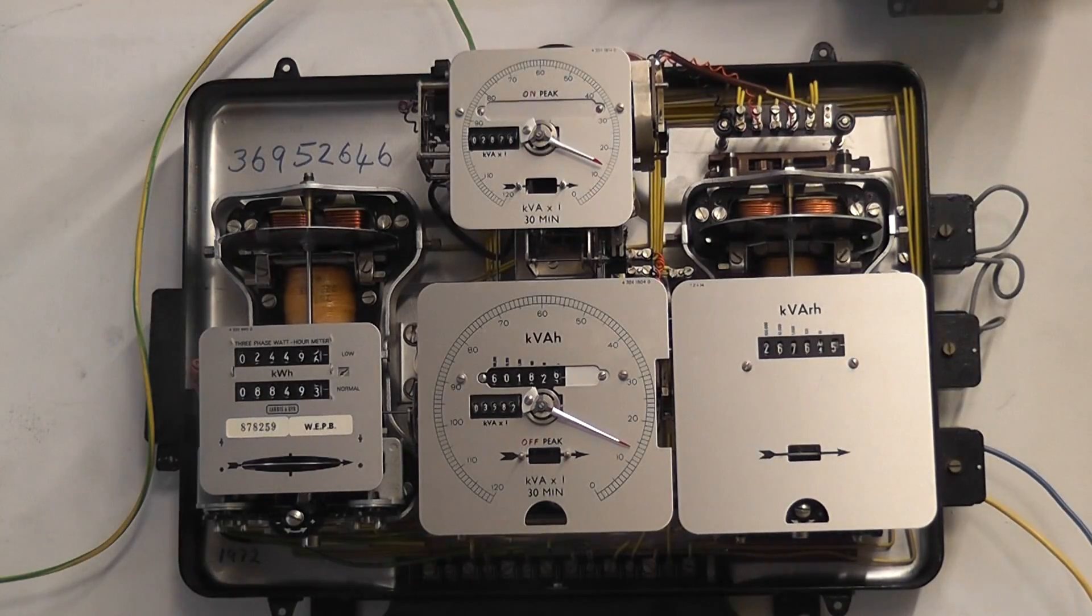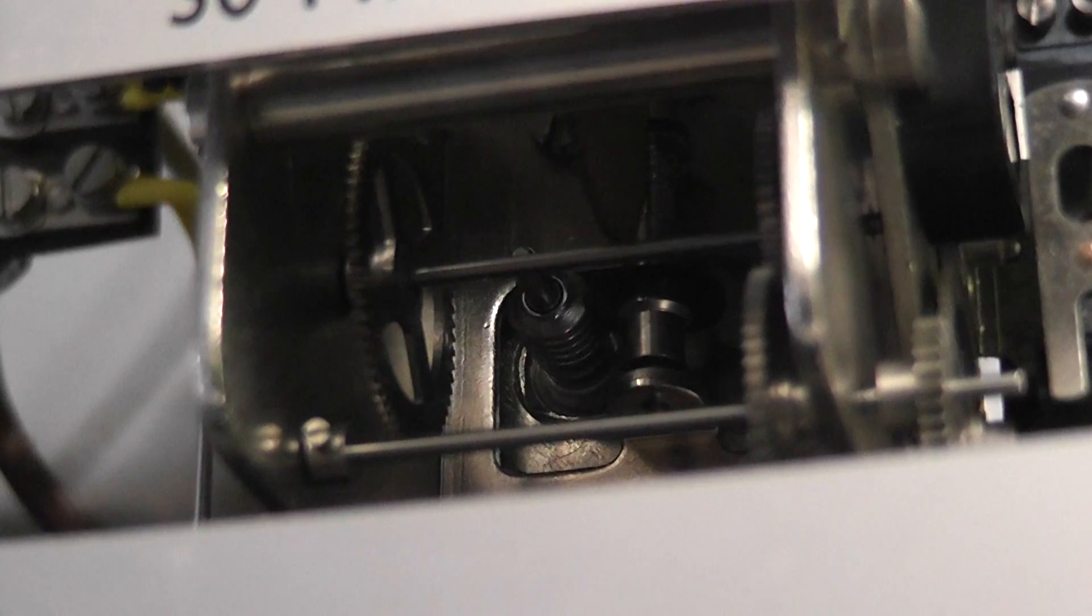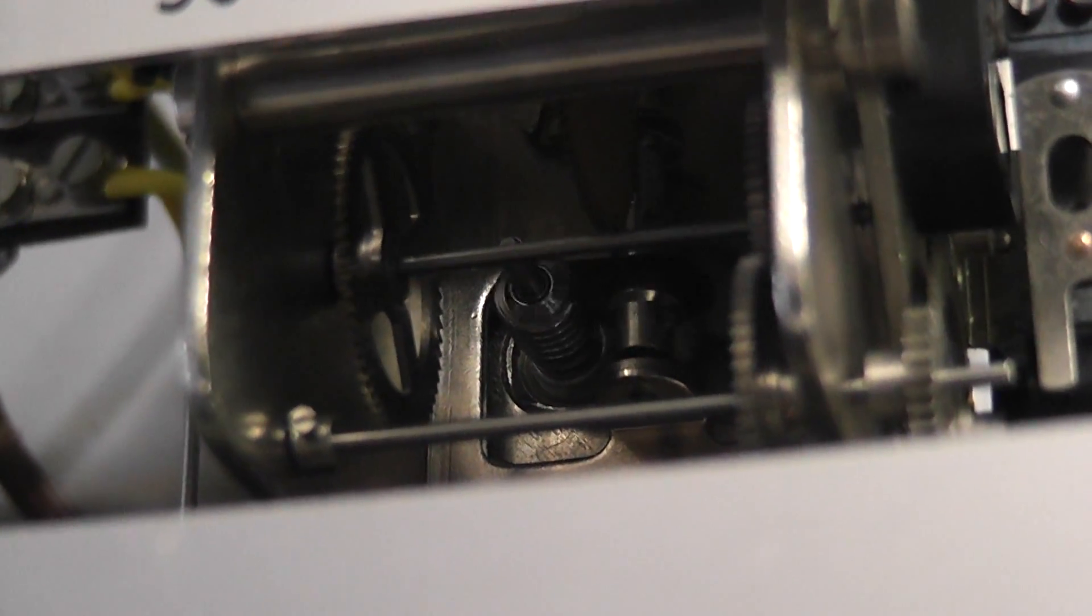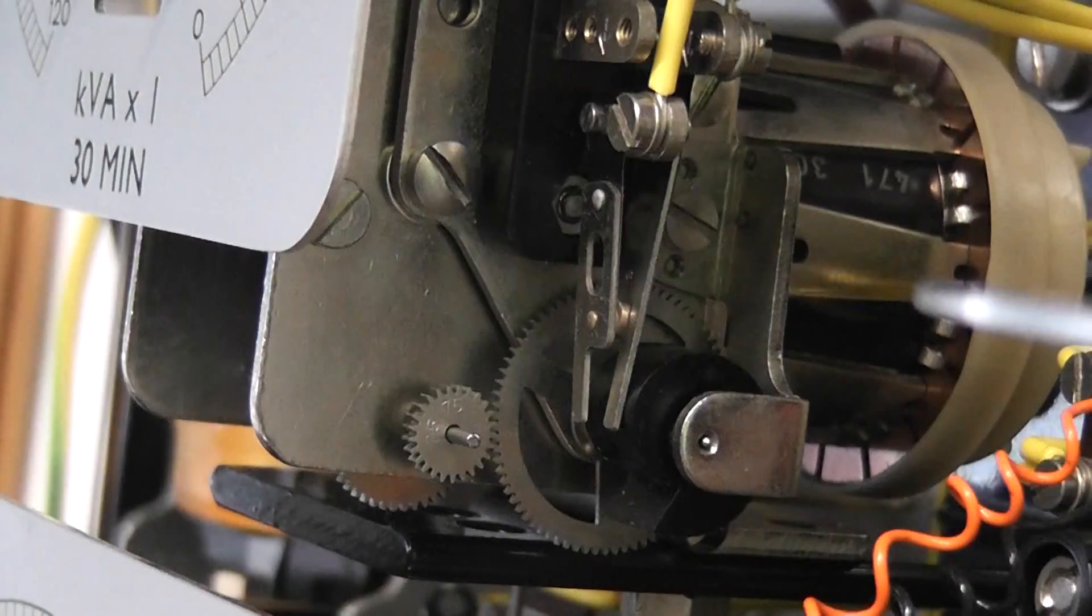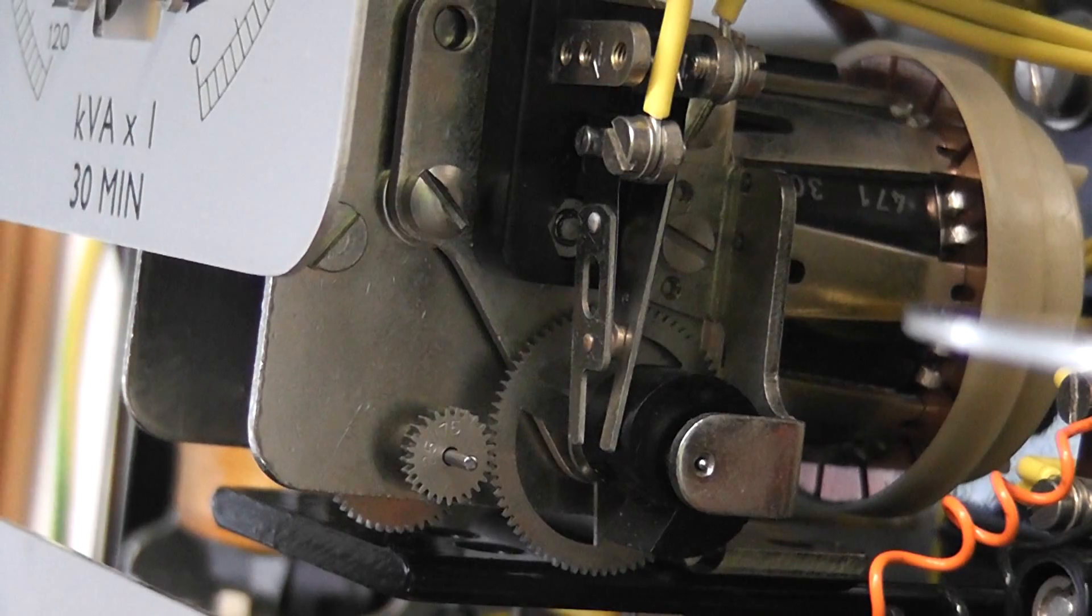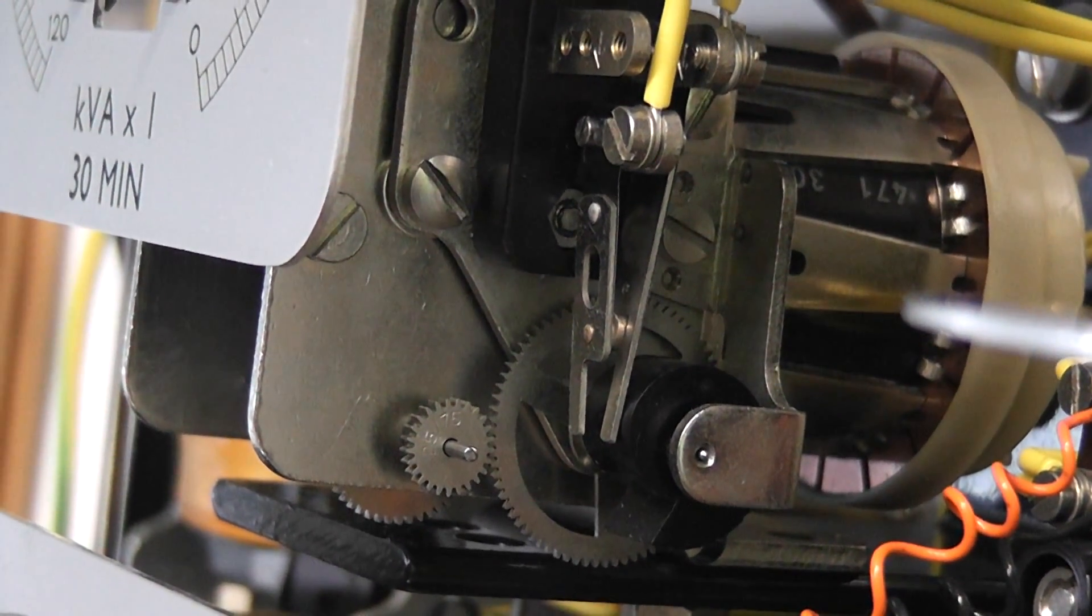Meter cover is being removed. You can see the timing motor. This is the cam and lobe for the reset every 30 minutes for the maximum demand registers.